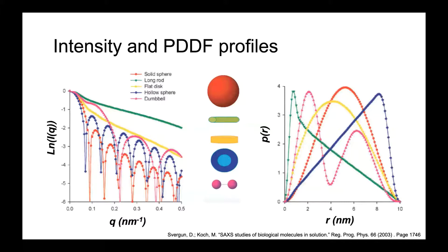Looking at different intensities and pair distance distribution functions for various particle shapes: a solid sphere in red, a long rod in green, a flat disk in yellow, a hollow sphere in blue, and a dumbbell-shaped particle in purple. You can already determine they'll have very different particle shapes from their scattering curves, but the pair distance distribution function provides the quantitative edge — determining particle size as well as the size of different features within that particle. This is very useful for catalysis, nanoparticle suspensions, or quantum dots.